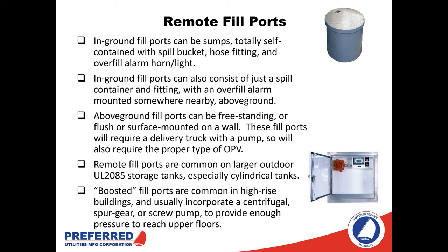Another critical part of the system is the remote fill port — this is what the fuel oil delivery person will be interacting with. They're typically not going to have access to the main tank itself or other controls, so this is the part that will indicate any alarm conditions like high level in the bulk storage tank. These can be installed in-ground or in-wall, and set up for gravity fill or pumped-in fill. At a minimum, we should have an audible and a visual alarm. The audible alarm comes on immediately once high level is reached to indicate to the fuel delivery person to stop providing fuel. The visual alarm, however, will not silence after acknowledgement — it stays on, so if somebody shows up 30 minutes later, they'll see an indication that the tank is already full or in high level.